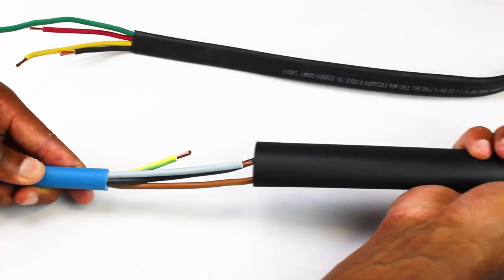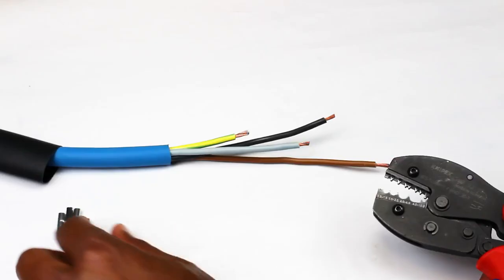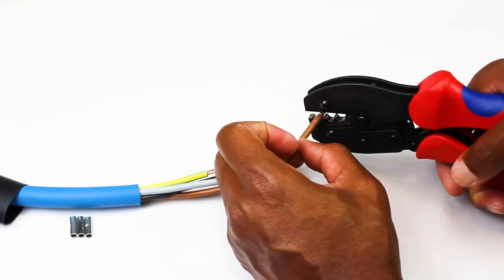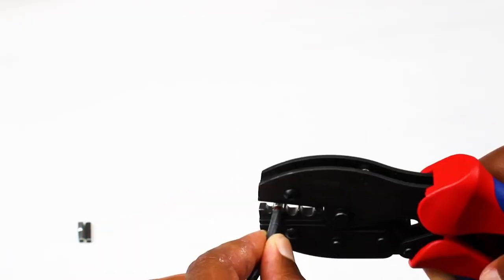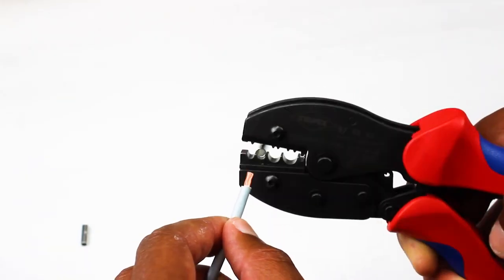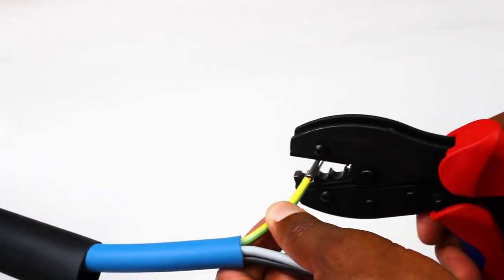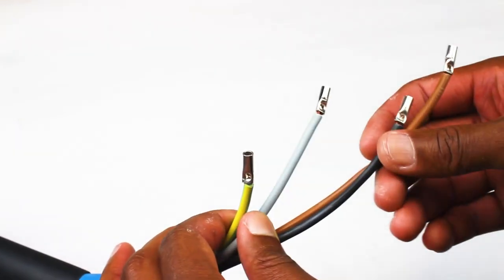Clean the cable jacket first before mounting the bigger shrinking tube. It might be comfortable to crimp the wires on one cable first and follow with the matching wires thereafter. Make a pull test of the crimping sleeves after crimping.